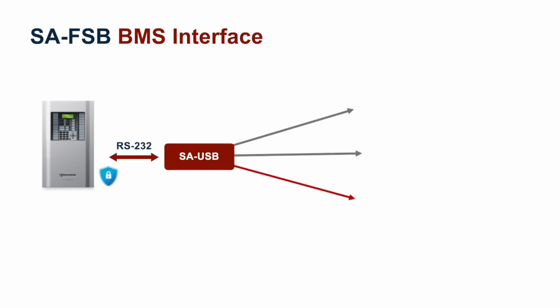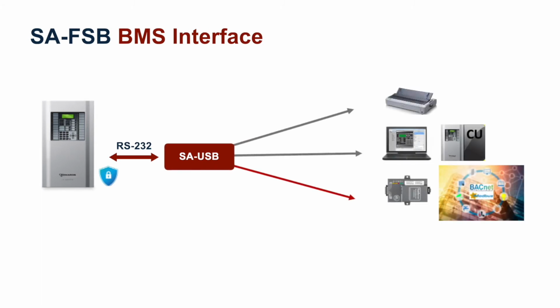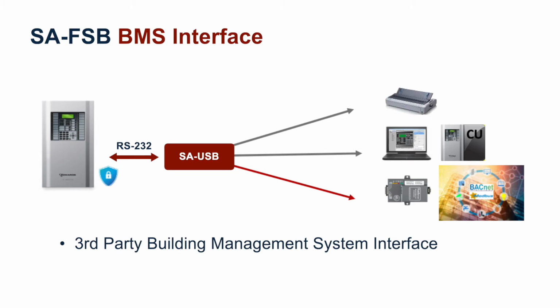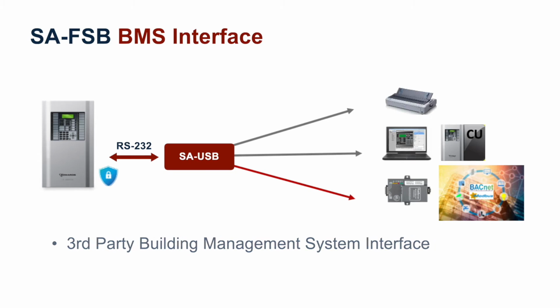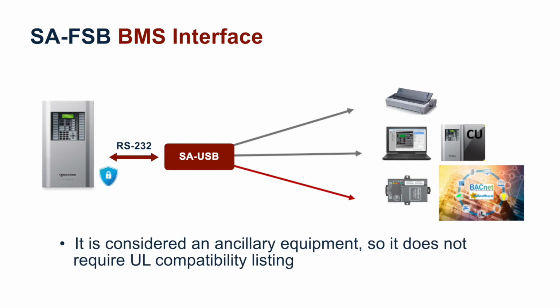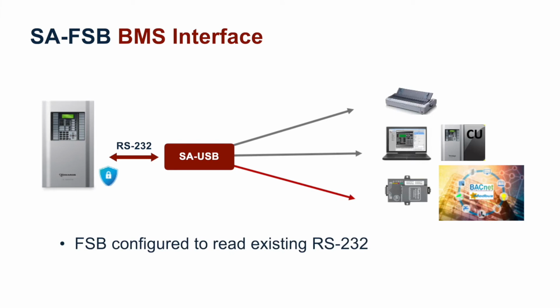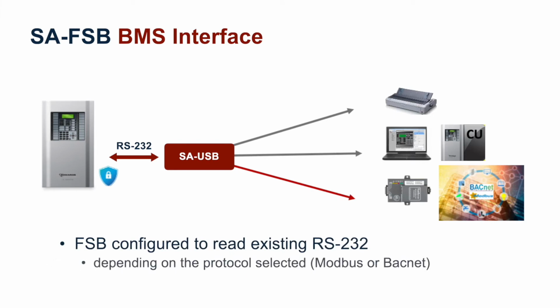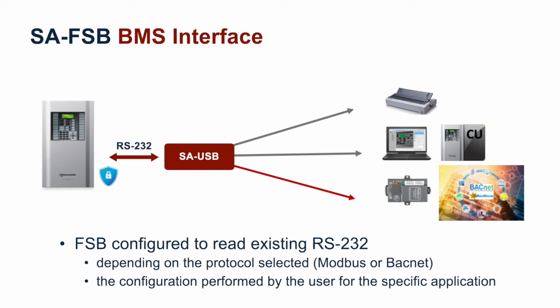Now the third product in the release is our SA-FSB, Field Server Bridge, new for the small addressable systems. This unit will provide a communication bridge between our small addressable system and a third-party building management system. It is considered an ancillary equipment, so it does not require the UL compatibility listing, but please note, use in non-ancillary applications may still require approval by your local authority having jurisdiction, your AHJ. The unit is designed to read the panel's RS-232 protocol and output the respective translation depending on 1, the protocol selected, Modbus or BACnet, and 2, the configuration performed by the user for the specific application.